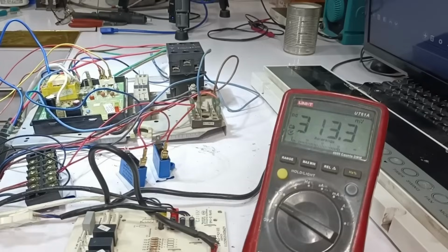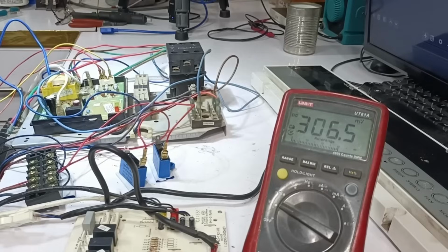At this point, the system is getting power on all 3 phases, but since it's from a single-phase line, all 3 are working on the same frequency with no 120-degree difference between them. As a result, the system detects that the required 6.6 millisecond phase shift is missing, which is why the orange error light turns on. Next, I'll show you how to confirm that everything else in the circuit is working.